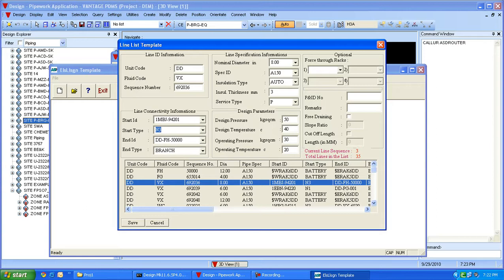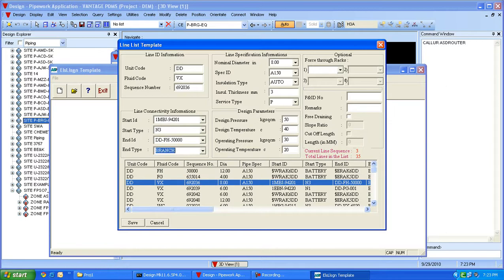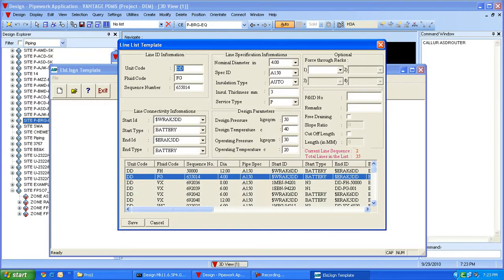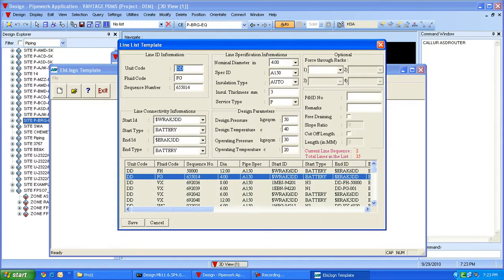The line list template is also linked to the line list so that the line from the line list in the pull-down menu for header can be selected, and its associated keyword is 'branch'. Users can also specify whether a line starts or ends at the battery limit, and by selecting a pipe rack location and the keyword 'battery', we can provide input for the line starting or ending at the battery.